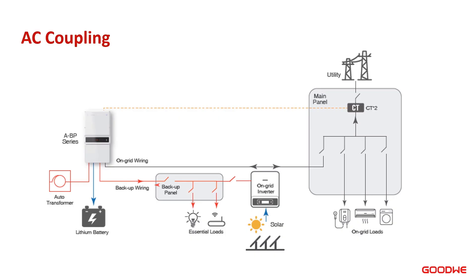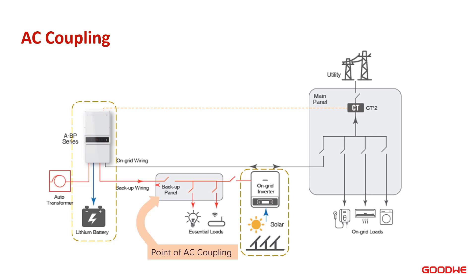Here is a diagram for AC coupling. We can see there are two parts to the system: on the left, a hybrid inverter connected with a battery, and on the right, a PV inverter connected through an AC connection — a backup panel in this case — acting as the point of AC coupling. So in this microgrid, we are seeing AC coupling between the hybrid inverter and the solar inverter.